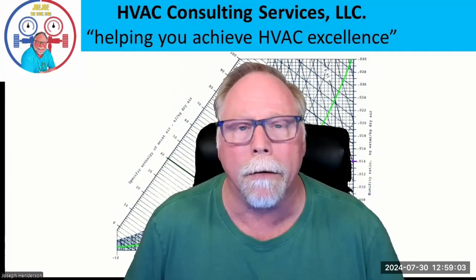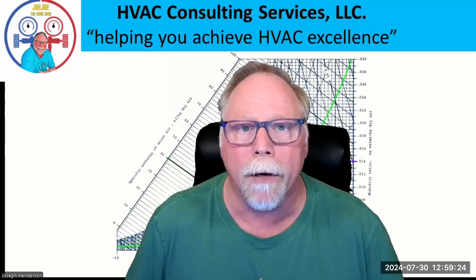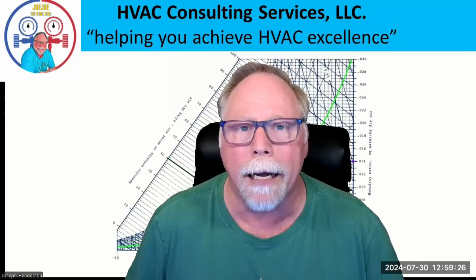Not been a big deal in our residential HVAC world for R22, R12, and R410A. They've all been just one thing. But now we got this dew point and bubble point for R454B. I wanted to just do a little video for it. It's really not complicated, it's very simple. Hit the like and subscribe to JoJo the HVAC Man.